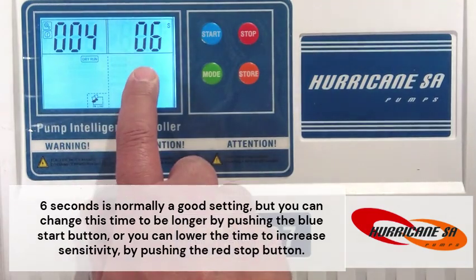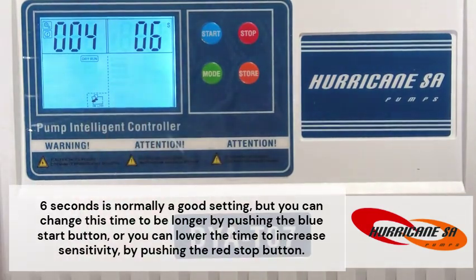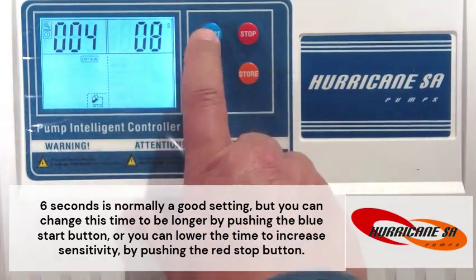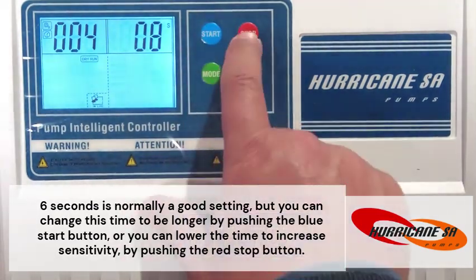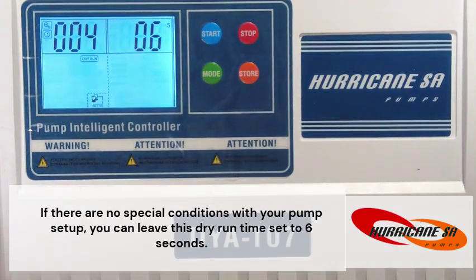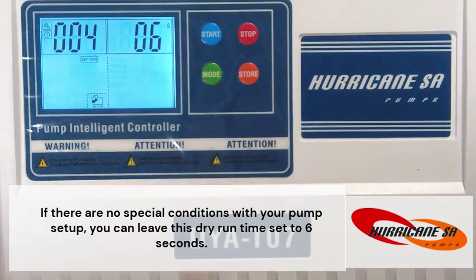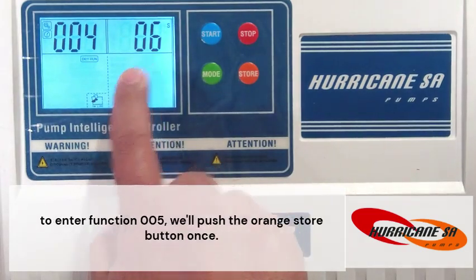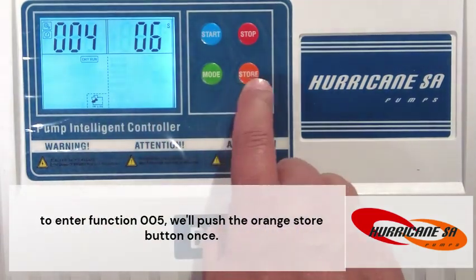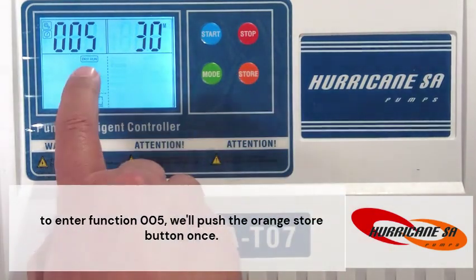6 seconds is normally a good setting, but you can change this time to be longer by pushing the blue start button, or you can lower the time to increase sensitivity by pushing the red stop button. If there are no special conditions with your pump setup, you can leave this dry run time set to 6 seconds. To enter function 005, we'll push the orange store button once.